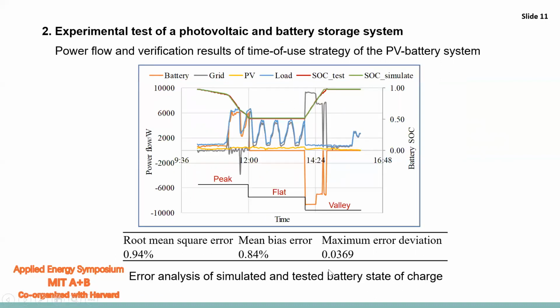For the time-of-use strategy, it first experiences a peak period where the battery is discharged to meet the load, then a flat period where the battery is neither charged nor discharged, and then valley hours, when the battery is charged by the utility grid at low cost to full state of charge. The maximum error deviation between the tested and simulated battery state of charge is about 0.04.